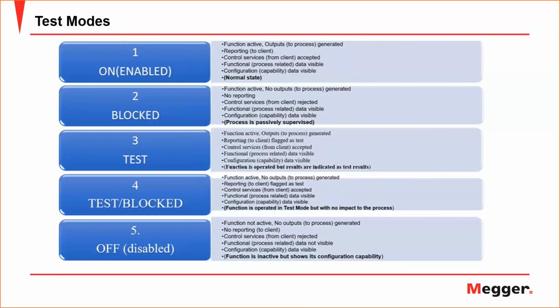And also the outputs of this process, if it's giving a trip or start contacts or operate conditions, will also be flagged as test or simulated values. So whoever is injecting and receiving the outputs from the IED will understand that these are simulated values being injected in test mode.